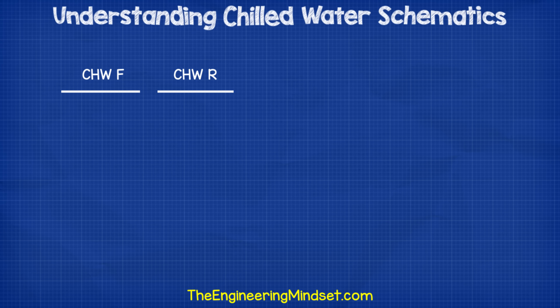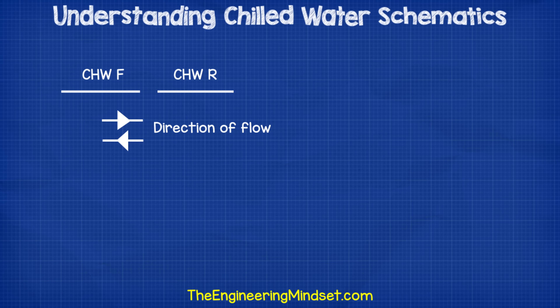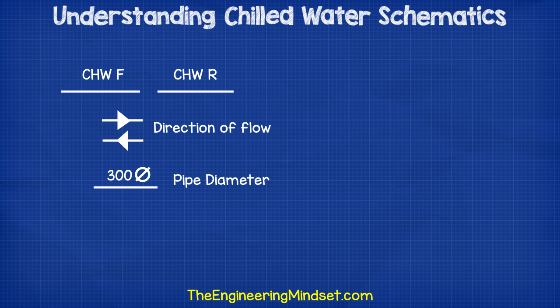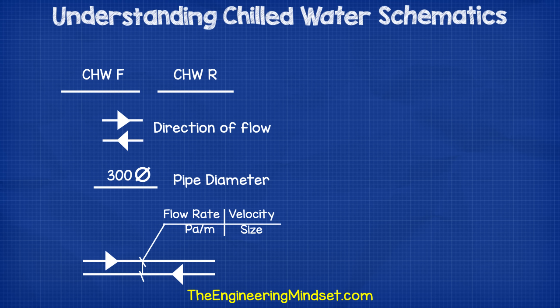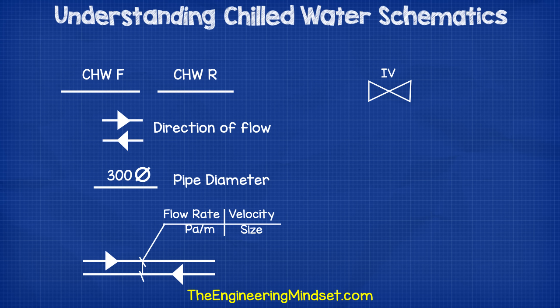Some important things to note about reading a schematic: the pipes will often have letters to help you identify which system it is, such as CHW or CND for chilled water and condenser water. They will also use F and R for flow and return. You can see the direction of the flow on the pipes just by these little arrows. The diameter of the pipe is sometimes listed next to the line. Newer designs might show you the designed flow rate, the velocity, the pressure, and also the pipe diameter. You'll also see letters around the valves to identify what type of fitting it is — for example, IV stands for isolating valve.